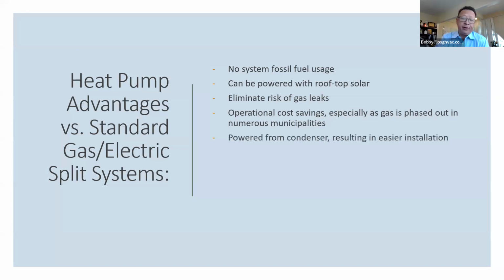Okay, another advantage for the modern day heat pump is that many of the manufacturers, if not all the manufacturers of mini splits, power their indoor unit from the condensing unit. So there's no need for separate power, much easier installation. The wire gauge is 16 to 18, so it's not very thick wire. And again, you do not need power at the fan coil. And like we talked about in the previous slide and the video, achieve both heating and air conditioning with one system.